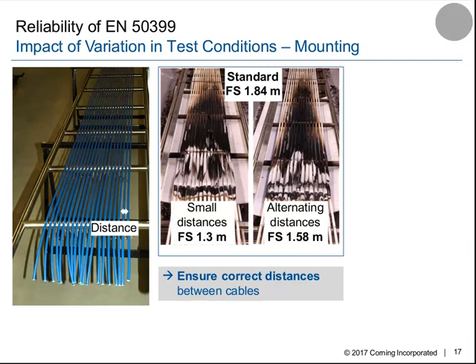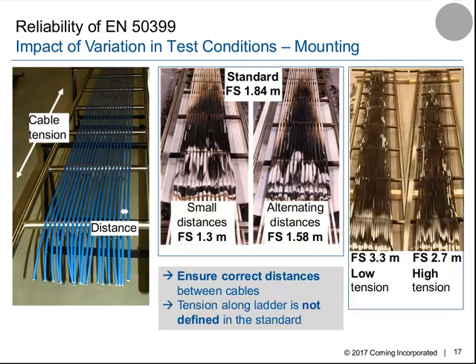The next thing was to look at alternating distances. What that means is that the overall width stays 300 millimeter as defined in the standard, but the distances are not measured accurately enough. So we have 7 and 13 and 8 and 12, something like that, millimeter distances. And what you see is that we found that the flame spread was lowered by approximately 30 centimeter just by applying alternating distances. Here we really want to highlight that it is important to ensure the correct distances during the mounting, because this can lead to variation.